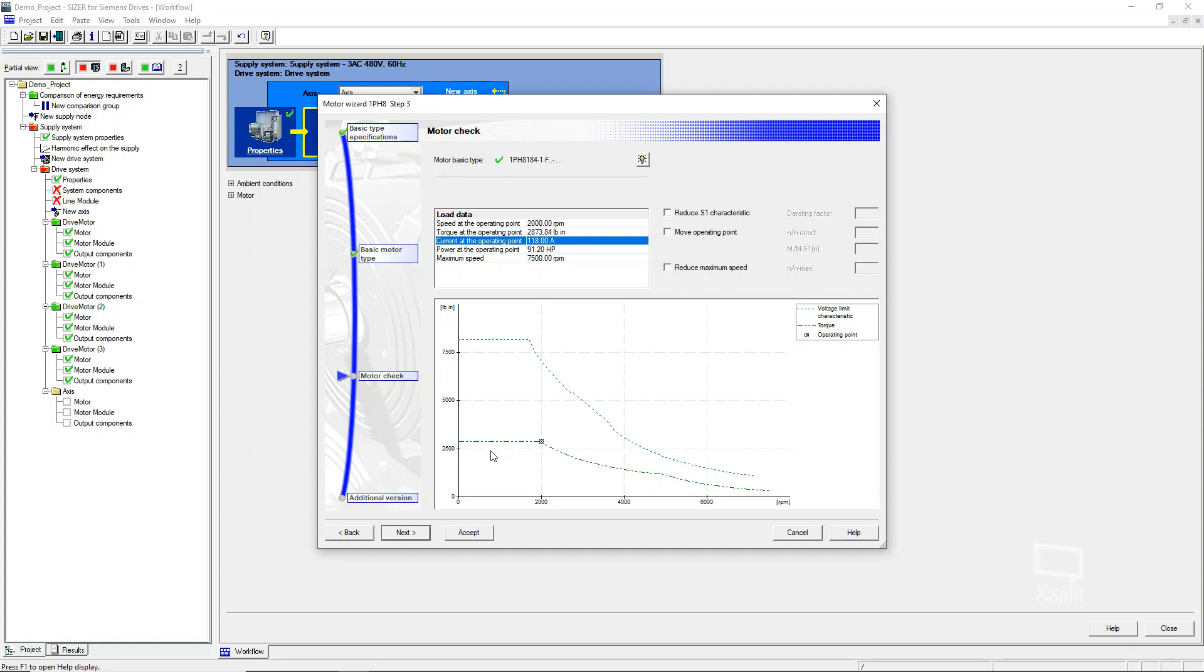Just kind of a side note, these 1PH8 motors are designed to replace your DC motors that have these really high torque capabilities at low RPM. These 1PH8 motors can do that too. So remember, this is an S1 curve, so it can do rated torque. So that 2873, all the way down to zero RPM and do that continuously. So these are hoist duty motors, but they are blower cool. Just keep that in mind.